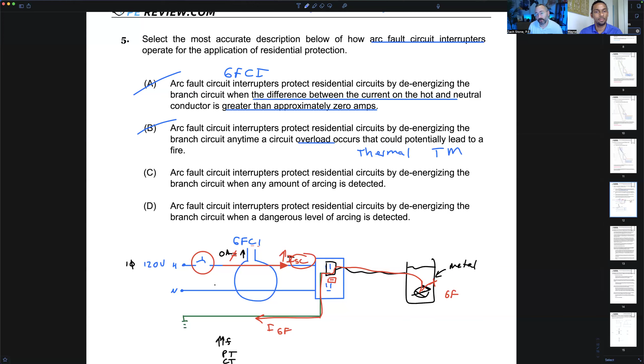B: protect residential circuits by de-energizing anytime a circuit conductor overloads. Nah. This would be the thermal region of a thermal magnetic breaker, which is what's designed for overloads. If you look at a thermal magnetic breaker, it's very similar to choice B, where your thermal region is really your long-time region, where we're only looking at a smaller number of amps compared to instantaneous for fault current. You've got a long time, say 400 seconds. That's an overload. So definitely not AFCI.